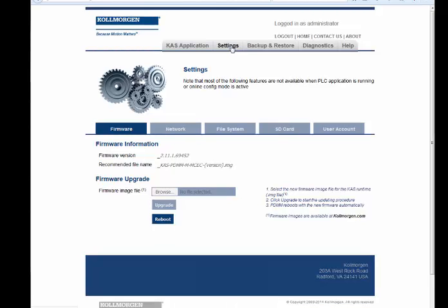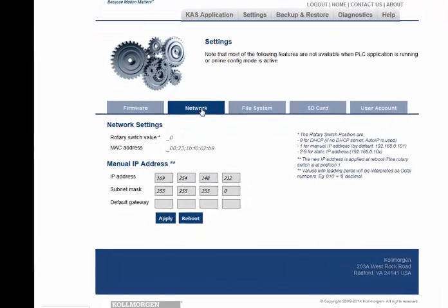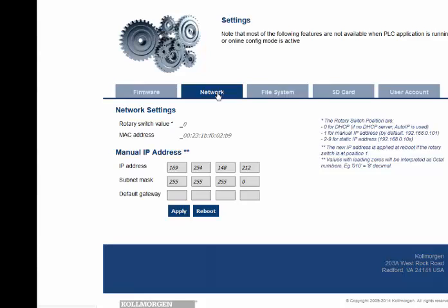In the Network tab, the controller's IP address can be set when the rotary switch on the controller's front face is set to 1. The default address is 192.168.0.101. Note, for the other 9 positions of the switch, position 0 will set up DHCP or Auto IP. Position 2 through 9 will set up IP address 192.168.0.102 to 192.168.0.109. The new IP address is applied to the web server when the controller is rebooted.